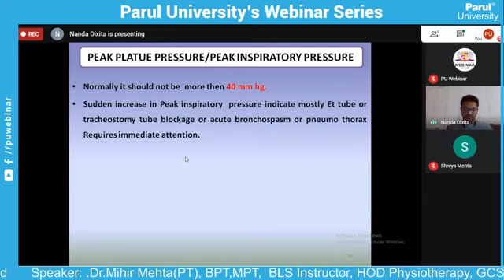So what is the PIP? If you see in the graph, this is a PEEP. First one is PEEP, which is a little bit higher than 0, that is 5 millimeters of Hg. Now, when a patient inspires, the pressure in the lung will rise, and the peak point in the inspiration is called PIP, that is peak inspiratory pressure. Now, if you breath hold or close the expiratory valve, do not allow the patient to exhale, then after some time the graph will plateau. This steady graph during inspiratory hold is called the plateau or peak plateau pressure.